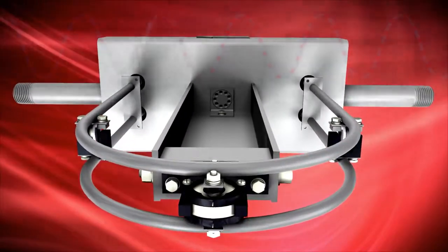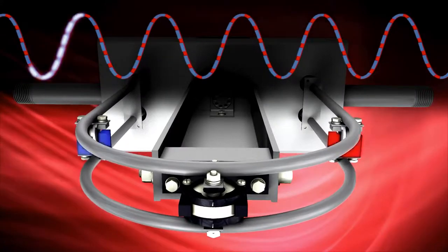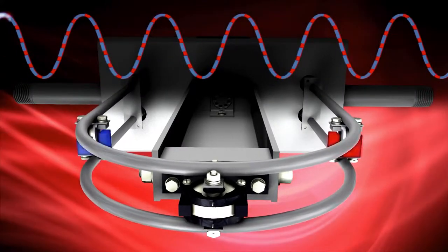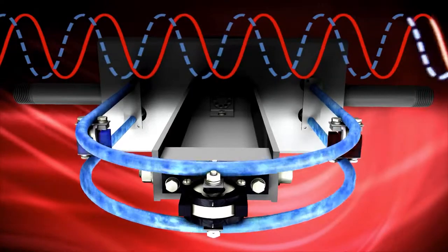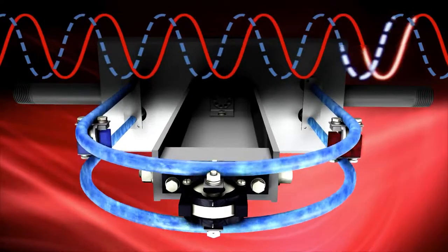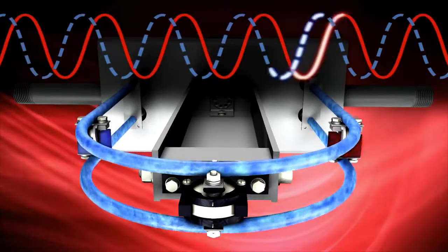Let's take a look at how the meter operates. A driver coil causes the tubes to vibrate at their resonant frequency. As fluid flows through the resonating sensor tubes, forces induced by the mass flow cause the tubes to twist, creating a phase shift between two millivolt sine waves.